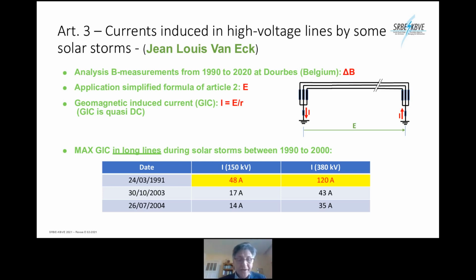In that case, when a long line is earthed over transformers at the extremes, a geomagnetic induced current, what we call a GIC, of 120 amperes at 400 kilovolt occurs in the neutral grounding points of these transformers. This long line grounded at the extremes is a theoretical concept. Taking into account the particularities of the Belgian grid, the GIC value, or the induced current value, will be reduced substantially. This happens in the next paper, which will be presented by the author Albert van Ranst.